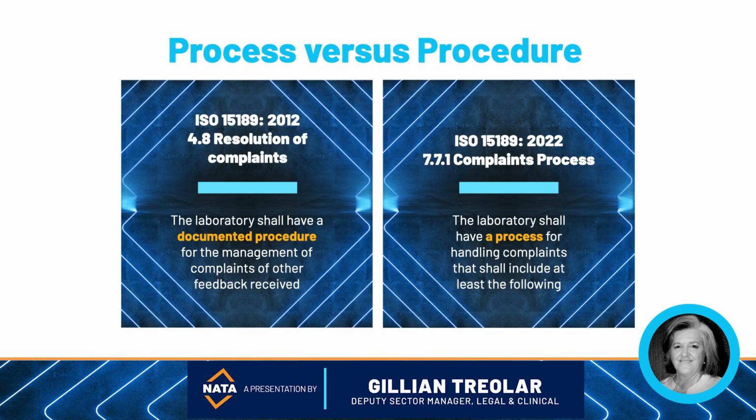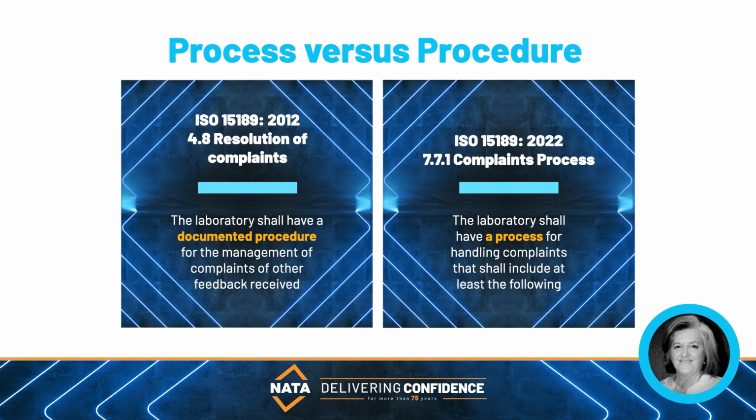And one final example, in the 2012 version of the standard, under the resolution of complaints, the lab is required to have a documented procedure. In the 2022 version of the standard, the lab shall have a process for handling complaints. It should be noted that not all prescription has been removed. The requirement for a procedure is still in the document more than 90 odd times.